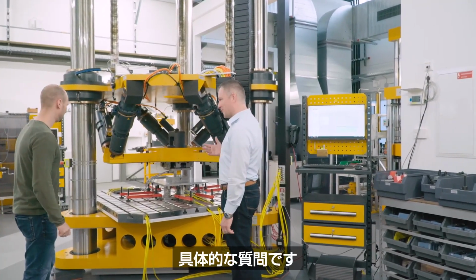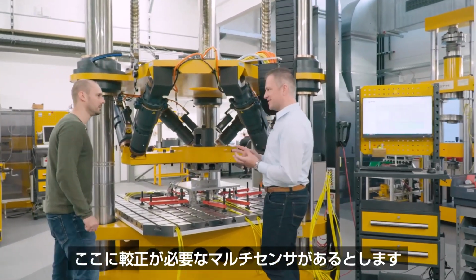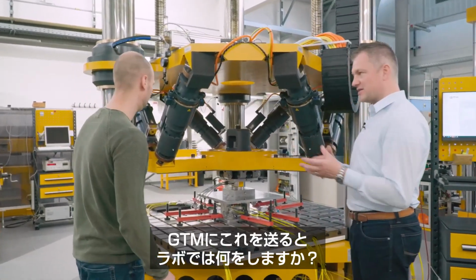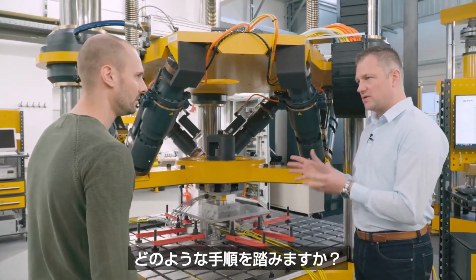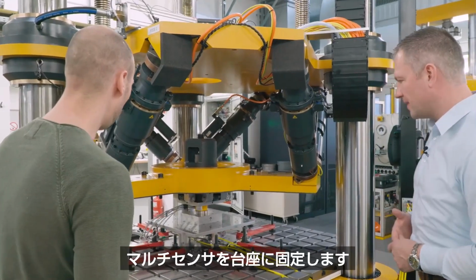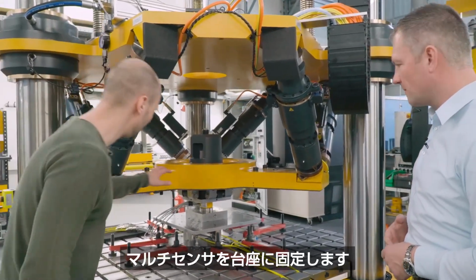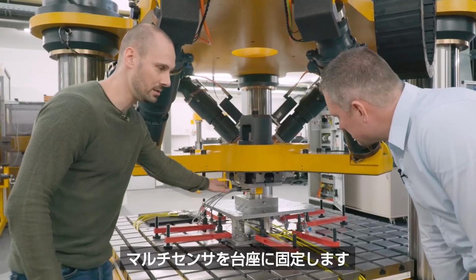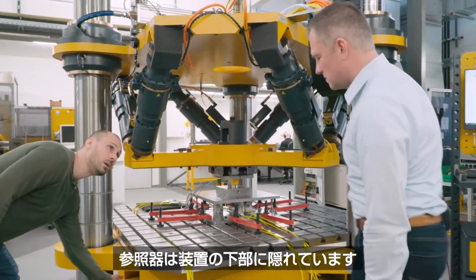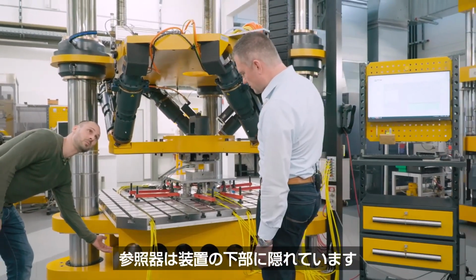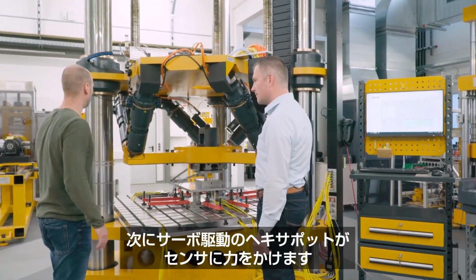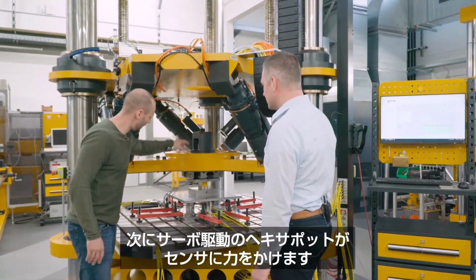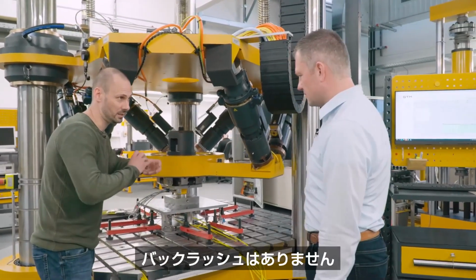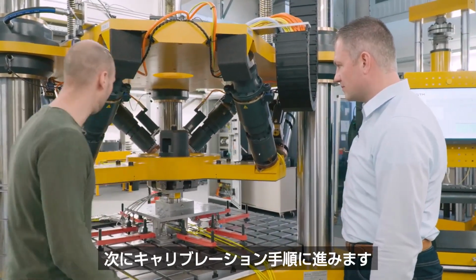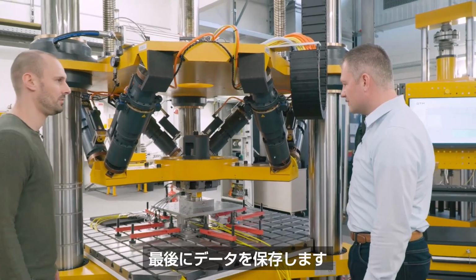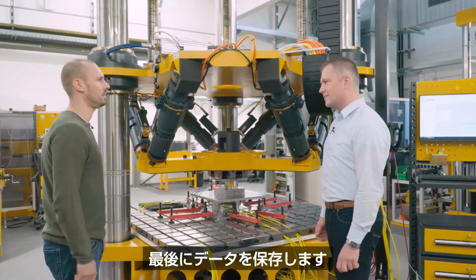Okay, and let's get practical. If I have a multi-component sensor that needs to be recalibrated, I send this to GTM. What happens in the lab? What are the process steps that you take? The multi-component transducer is fixed on the groove plate, with our reference system. It is hidden in the bottom of the machine. Then the servo-driven hexapod is coupled with the transducer, backlash free. Then the calibration procedure can begin. After that, you can save the data.